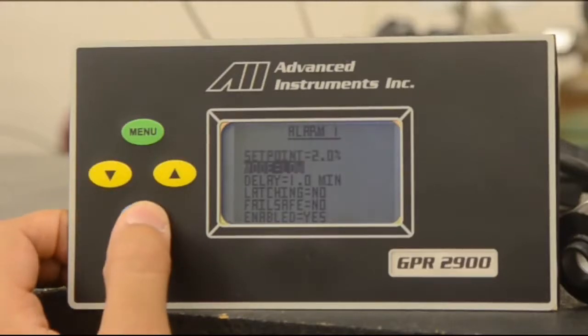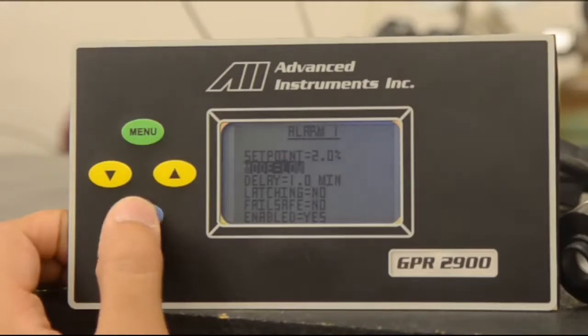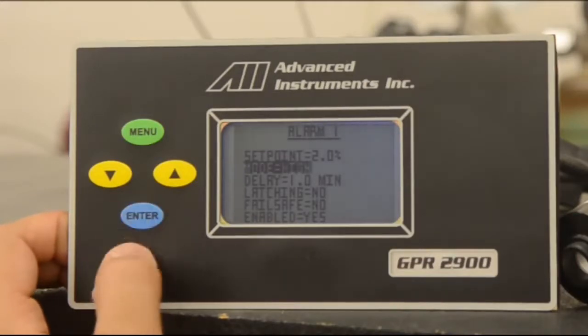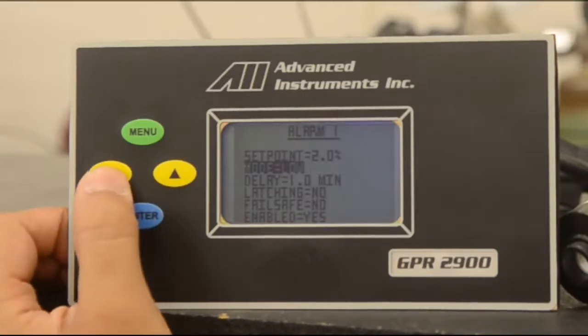You also have the option to set the mode for either low or high. Right now the alarm is set at 2% low. So if the reading were to drop below 2% oxygen, the alarm would trigger. Hit enter to set to high, and again enter to set to low.